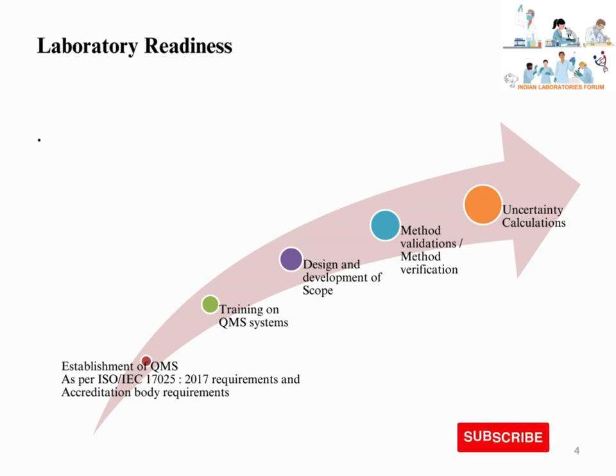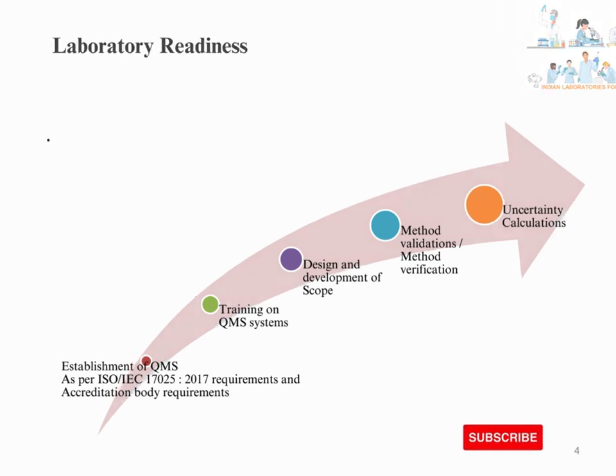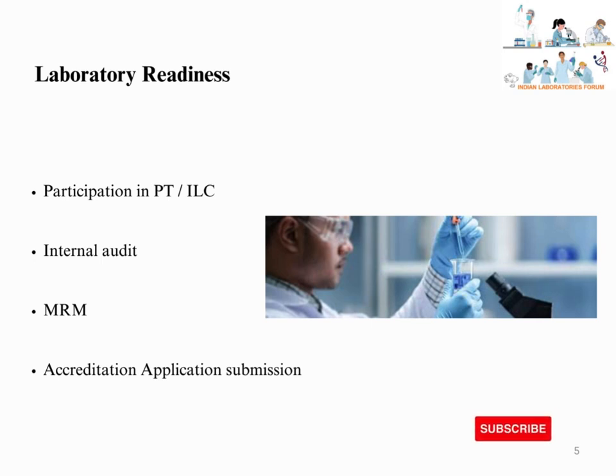The laboratory should decide on the products and test parameters for which it is willing to apply for accreditation, and design and develop the scope based on business needs. Upon designing the scope, the laboratory should perform method verifications or validations and calculate the measurement uncertainty for each parameter applying for scope of accreditation. Upon completion, the laboratory should participate in proficiency testing programs from ISO/IEC 17043-accredited PT providers, or if no PT providers are available, initiate or participate in an interlaboratory comparison program.